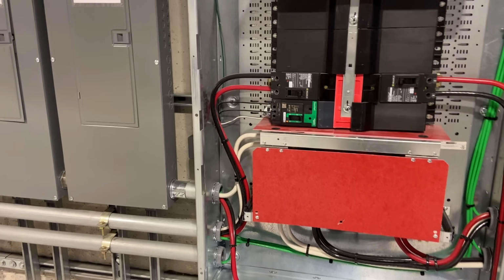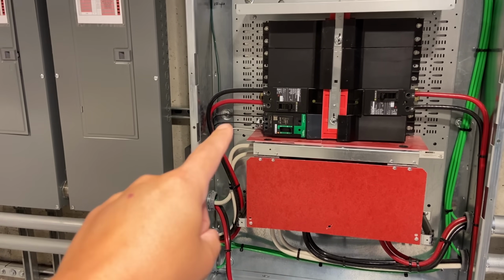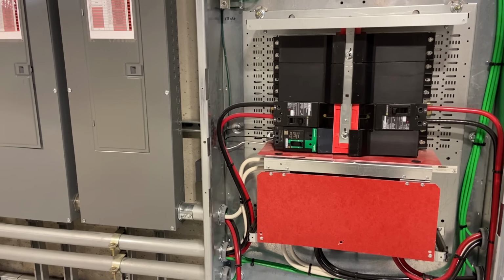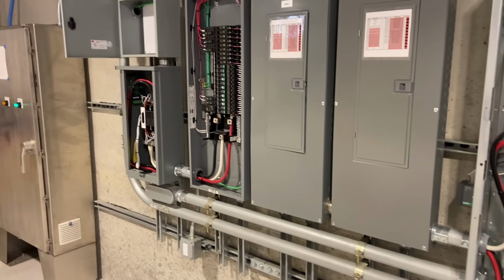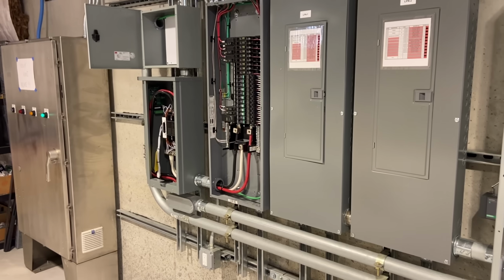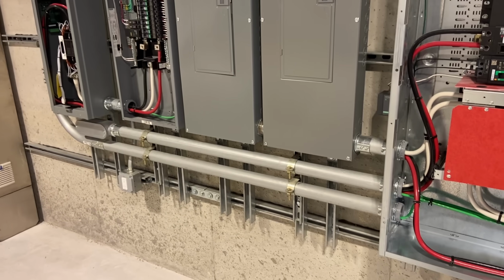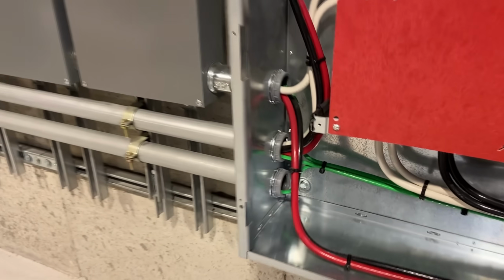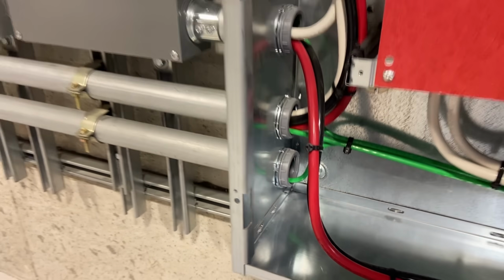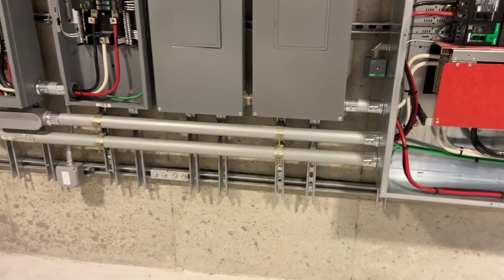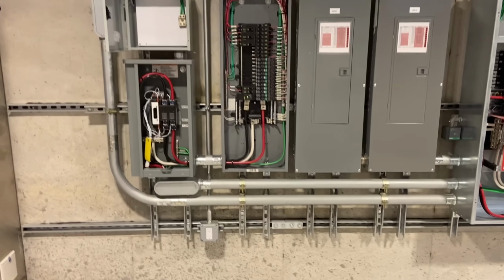So the original concept was I had this 175 amp circuit breaker feeding the ATS, and that would automatically transfer the power for that essential panel. Then if I had a long-term outage, I could transfer the whole house using a back-fed breaker, just like an interlock kit in a regular house. That is still the plan. I just want to make a custom transfer switch.